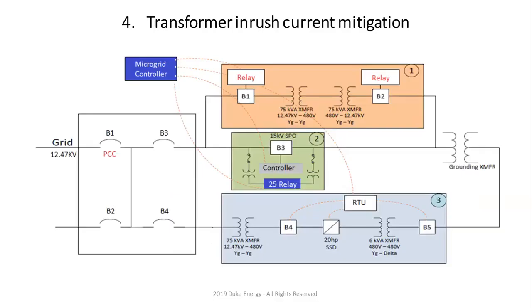And this is essentially the implementation that we currently have in order to reduce the inrush current into the grounding transformer, right? Look at the B3, that's our B3, right? And if you look at the straight line that has a controller and 25 relay, that is the relay that actually energizes the grounding transformer based on the residual magnetism, right? We have 2 different controllers that we're currently testing.